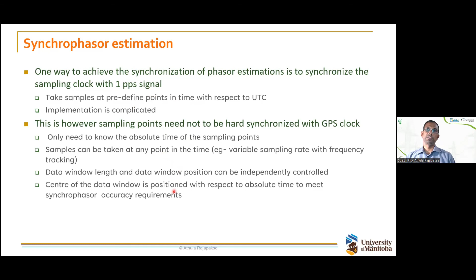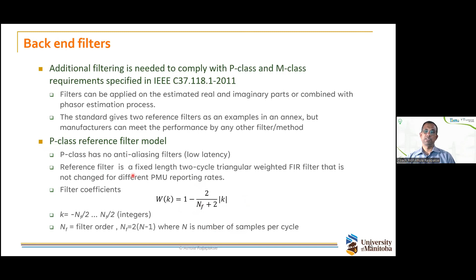Remember I mentioned two things, P class and M class. To satisfy these measurement classes, you need to estimate the phasors and then apply an additional filter to the real and imaginary parts. For example, the standard gives what they call a reference filter model, which you can consider as an example of a filter you can use, but you can use a different type of filter — the only requirement is that you satisfy the accuracy requirement. The standard says that if you use this filter, you can achieve the required accuracy level. For the P class, it's a very simple filter; the filter coefficients look like this and it spreads over a two-cycle window.